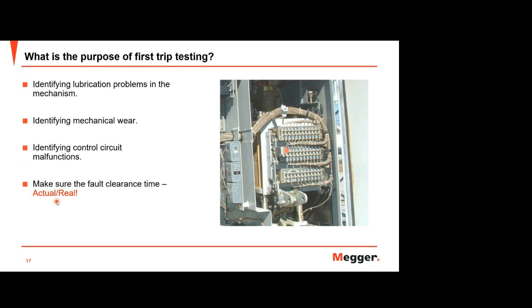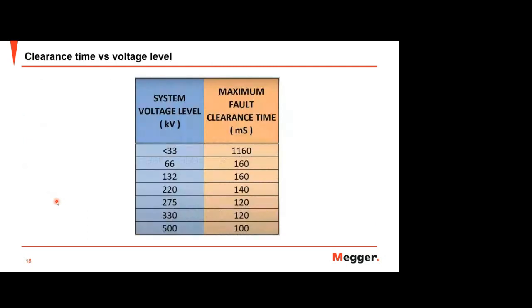And the last one, I think this is also one reason, we can make sure of the fault clearance time in actual or real condition. Because as you know, based on this table, system voltage level versus fault clearance time, this varies a lot. A higher voltage level gives a faster maximum fault clearance time. For example, for a system below 33 kV, the maximum fault clearance time is mostly around 1.1 seconds in total. But if you have a higher voltage system, for example 500 kV or maybe 275, of course the clearance time will be reduced, meaning it should be faster compared to the lower voltage level. So with first trip, you can make sure your total clearance time is still within what you expect.